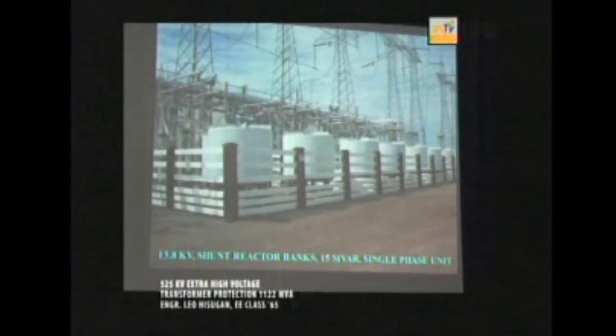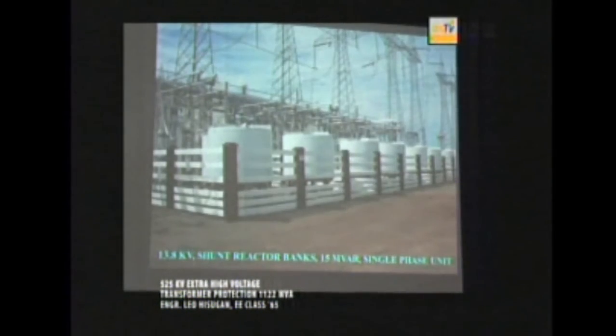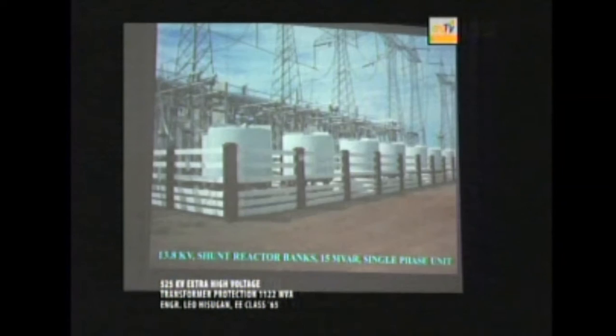During light load, the voltage at the end of the line, for example in this Los Banos, goes from 525 to like 530. So we energize these shunt reactor banks. This is a single phase unit on the 13.8 kV bus of the system. It will become a load in your system that will lower the voltages dramatically. From 530, it will be lowered to like 520 or 519 or 512, whichever is your required voltage at that station. So shunt bank reactors are very, very useful and sometimes very troublesome too, but most of the time they are used for our voltage correction.